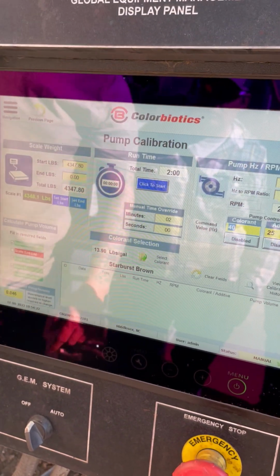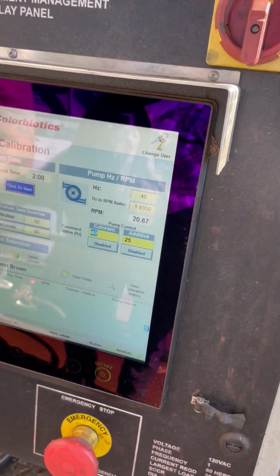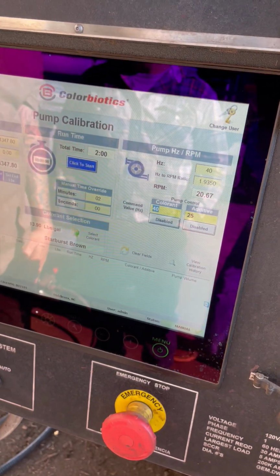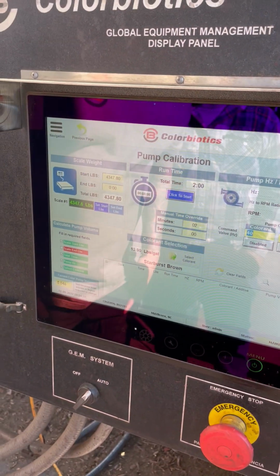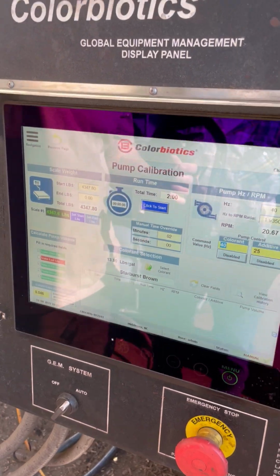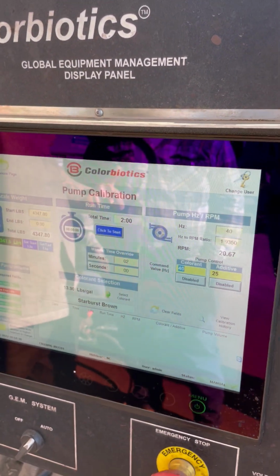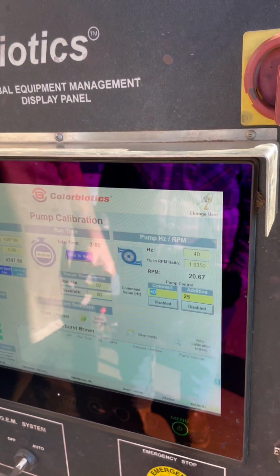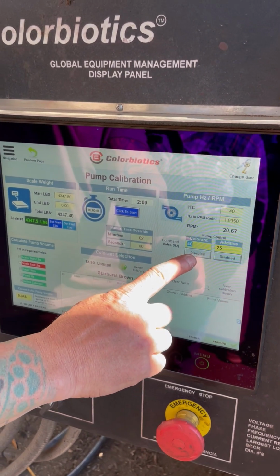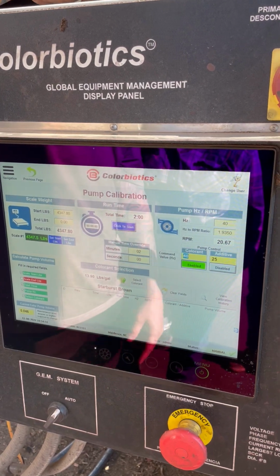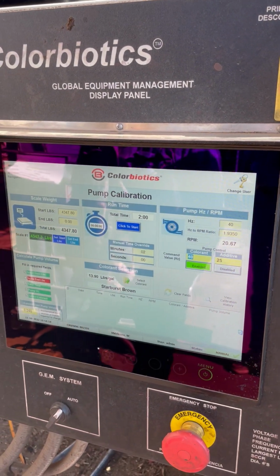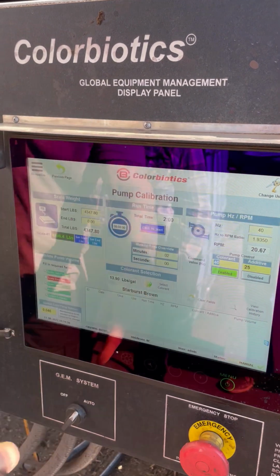The last thing we need to do is check off how much end pounds we have. But in order to get an end pound, we got to run the pump at 40 hertz, on auto. Then what I'm going to do is take a stopwatch, or use my phone, and run it for 2 minutes. In order to turn the pumps on, this disabled button, all you got to do is hit that and start your stopwatch at the same time. And if you double check, we're running at 40 hertz.